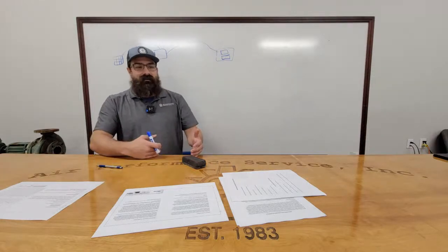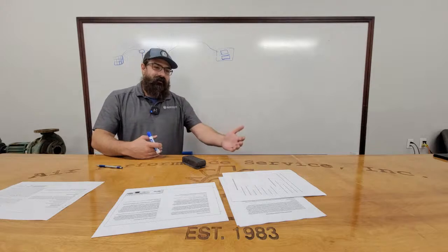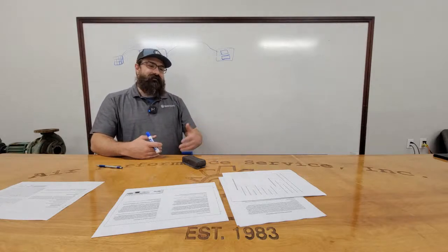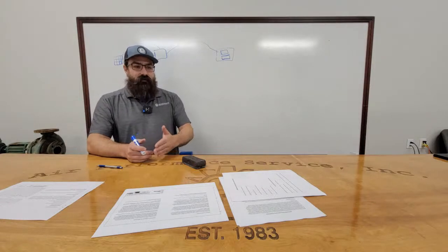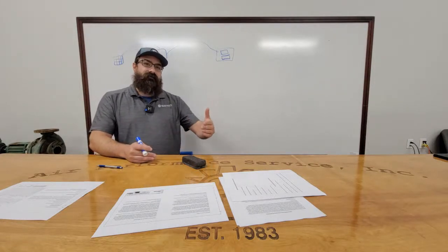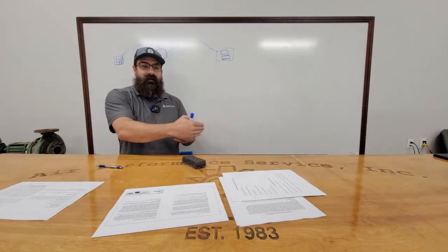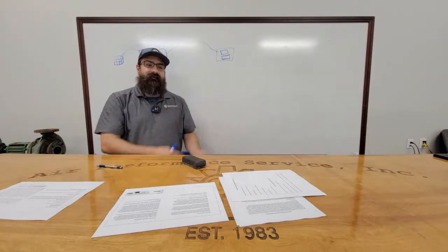Or you can go look at the load on the boxes. They're all set to 85 degrees. Their load is going to increase when they get above 85 degrees. So you use the load to bring it on. Or you use the bypass function where the box occupies itself. You're monitoring that mode, and then you bring on equipment, right? They all do the same thing. It's just different paths to get to the same thing. The end result's the same.